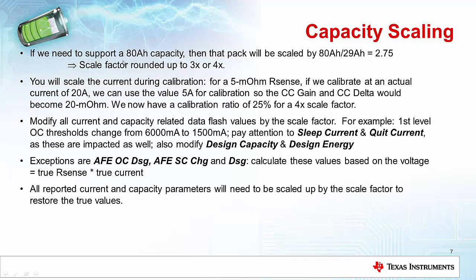You basically will scale the current during calibration. So for example, if we're using a 5 milliohm sense resistor and we're calibrating with an actual current of 20 amps, we instead tell the software that we're only using 5 amps. And so then when it calculates the calibration values, it effectively thinks that you're using a 20 milliohm sense resistor. And so then we end up with a calibration ratio of 25% for a 4x scale factor.